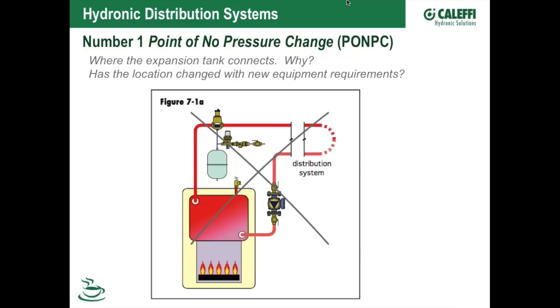Years ago, cast iron boilers came as package boilers sent to the job site in a crate with the pump mounted on the boiler. For various reasons they thought they needed to put the pumps on the return side. We always want our air elimination device — ideally a micro-bubble separator — at the hottest point in the system, immediately coming out of the boiler. That's the best place to get air removal, where entrained air gets driven out of solution.